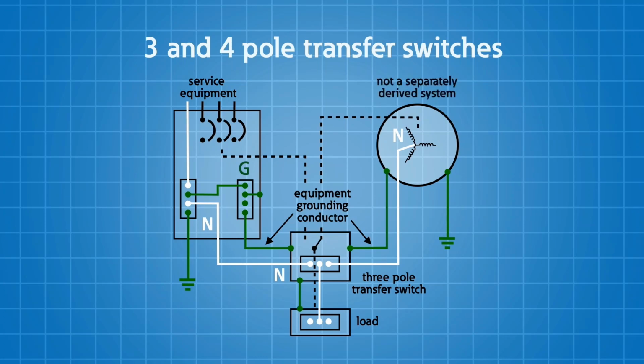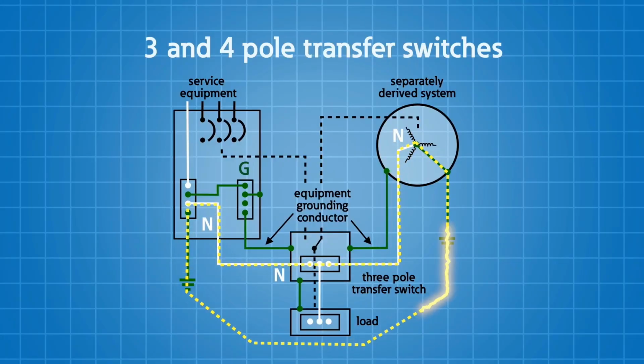But you must be extremely careful on how you operate a system like this, because the return current for the generator neutral will flow back through the other separately derived system or transformer. This is especially important for the electrical workers who will be servicing the equipment.